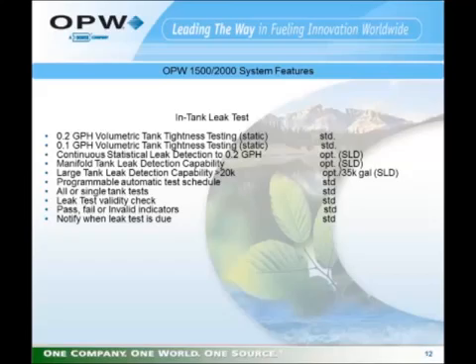Both units can perform leak testing on tanks that are larger than 20,000 gallons but less than 35,000 gallons with the optional SLD function. Both support programmable automatic test schedules. You can program to test all or single tanks. They both perform validity checks on the leak tests that they perform and will issue either a pass, a fail, or an invalid or inconclusive indication on the test. And both can be programmed to notify you if a test has not passed and a test is due.